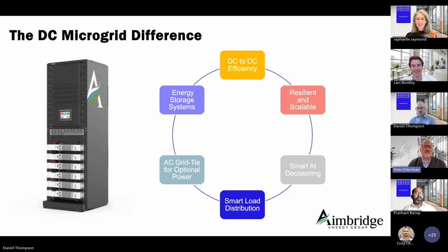We have picked a strategy to stay low voltage DC wherever it makes sense, and there are certainly constraints there in terms of transmission or conductor losses at low DC voltage and high current at a class 2 level. In my years of data center and telecom experience, fault managed power and high voltage touch-safe implementation was a big talking point, because of the significant energy density where you're approaching 100 kW per equipment rack, and you want to distribute at high voltage. How do you do that safely and effectively with management? So for now we're watching that. We don't have a dog in that fight yet in terms of our product implementation, trying to stay at a low voltage, fairly low kW level. But it's interesting to watch.